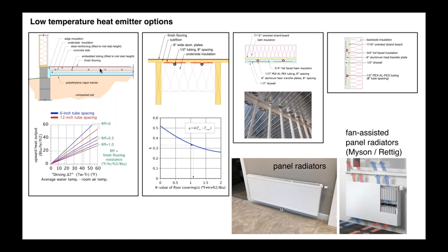I do show a high mass slab system. Now, there's going to be applications, for example, a service garage or a workshop, or even something like an aircraft hangar, any type of a commercial slab on grade building with a relatively stable heating load. Floor heating in a slab could be supplied from either a single air to water heat pump, or if you get up into capacity ranges, perhaps multiple air to water heat pumps. You want to keep the R value of any covering low. My suggestion, nothing higher than an R1 over the top of that slab. A bare slab or a stained slab, painted slab, ideal. If we get into underfloor tube and plate systems, nothing wider than 8-inch tube spacing, 5-inch or 6-inch wide plates.